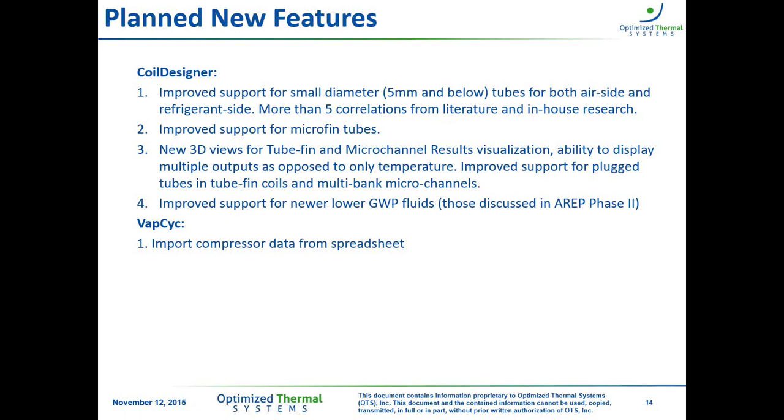And at OTS, we're working to develop two new correlations for airside heat transfer and pressure drop of slit fins and louvered fins with 3 to 5 millimeter diameters. So this is very similar to the CFD-based correlations, the two that were just added, but this capability will be added in one of the next two releases, depending on how that project finishes, and that will allow you to simulate slit fins and louvered fins with these small diameter tubes. Previously, that hadn't been really readily available. There hadn't been any correlations that really comprehensively cover that whole range of different geometries and fin patterns. Now that can be simulated relatively easily once those correlations go in.